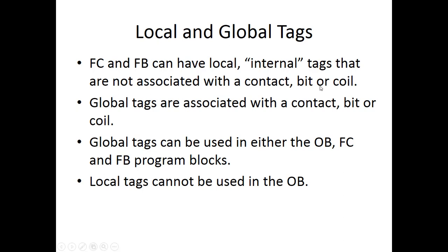Global tags are associated with a contact, bit, or coil. For example, you have a global tag called pushbutton1 — you can use that as many times as you want in the program. But what that's saying is physically, in the real world, connected to the PLC, there really is only one pushbutton. When you push that button, all the contacts associated with that will close. It's okay to use that for an input, but if you're using it for a bit or coil, best practice is to only use those outputs once in the program for troubleshooting.